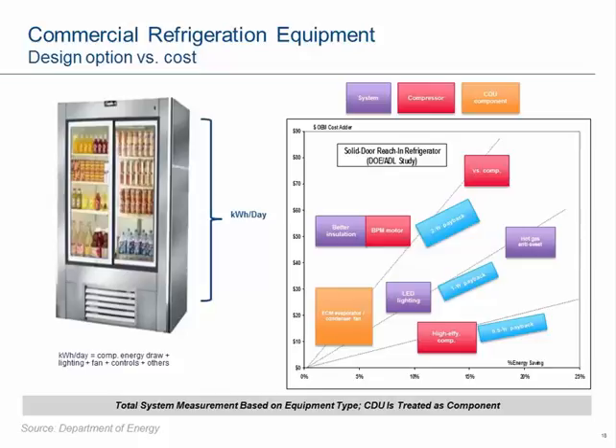The payback chart on the right comes from a DOE study in conjunction with A.D. Little that's been around for a while. Across the bottom is shown the percentage of energy savings at the system level for different design options that are available. In this example, we're showing a solid door refrigerator. This picture looks different for every configuration, whether it's a refrigerator or freezer, and as Ani described, there are different classes with doors being opened. Up the left side, in this study, is the cost adder that the equipment manufacturer would have to add.